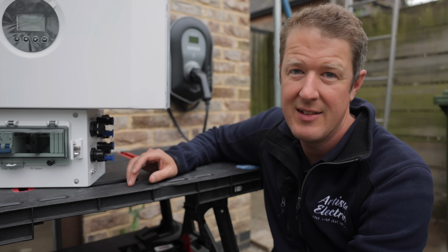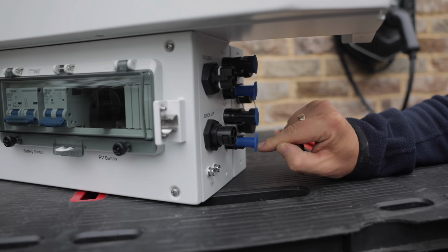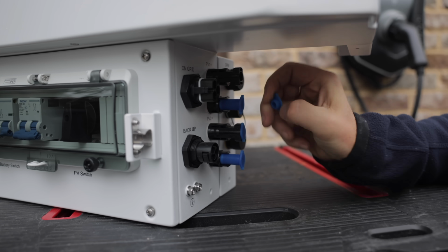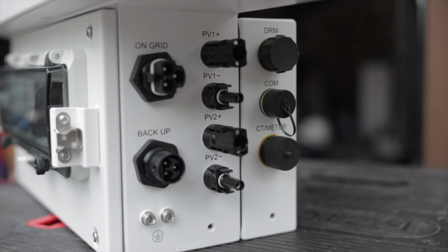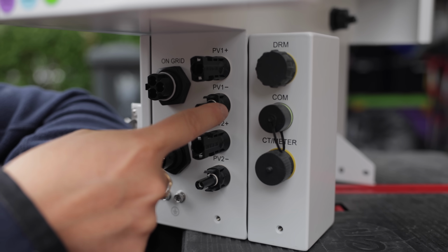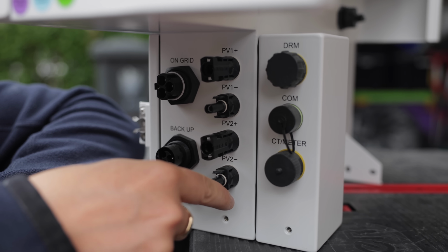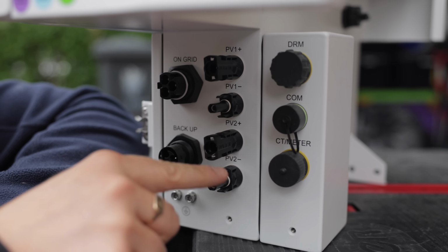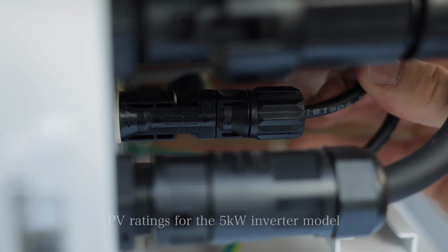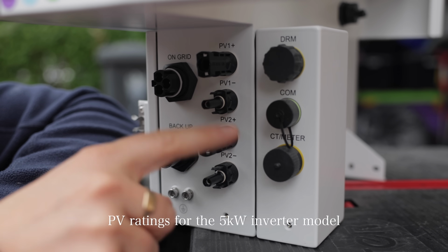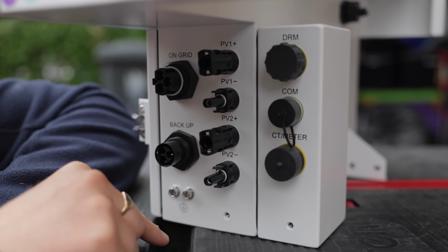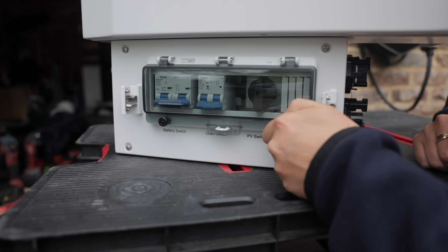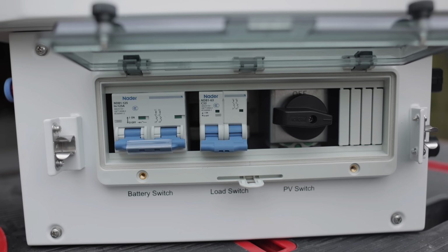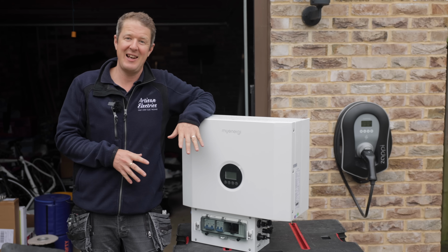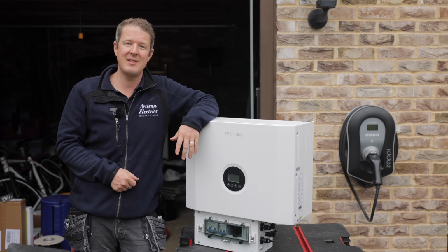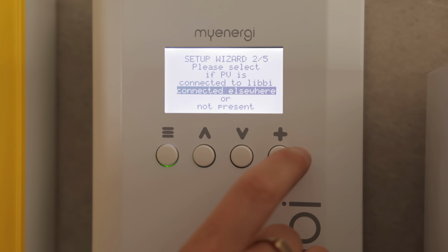So when you've got PV connected directly into the Libbi, these are the inputs that you're going to use for your MC4 connectors. Now it's possible to connect 2 strings of DC cables to the Libbi. So this is PV1 plus and minus inputs, and this is PV2 plus and minus inputs. So if you've got 1 string, you would use these 2. If you've got 2 strings, you would use both sets. And each MPPT string can take 3,250 watts of panels, or 3.25 kilowatts, for a total across the 2 strings of 6.5 kilowatts maximum DC peak wattage. You've also got an inbuilt DC isolator switch here to turn the DC side on and off as needed. So obviously that's when, in this case, you would select PV is connected to the Libbi. But let's go back to the setup wizard at the previous site. In this case, PV is connected elsewhere, so we select that.